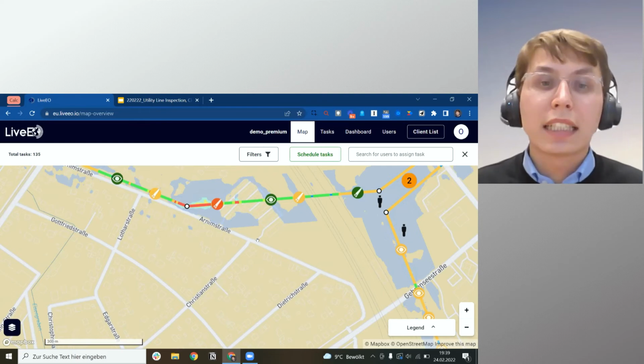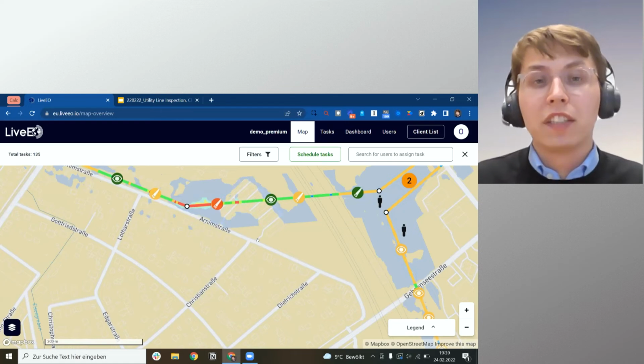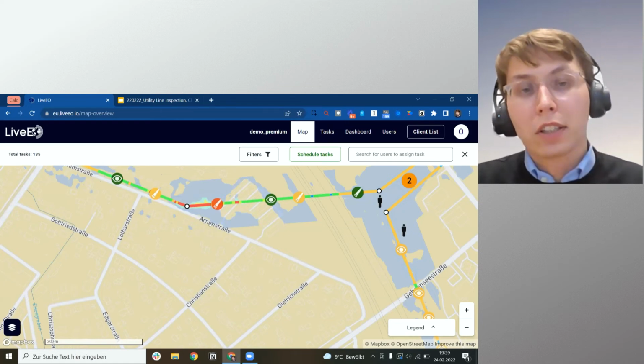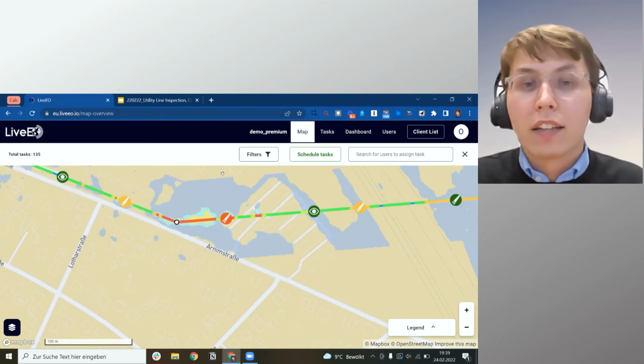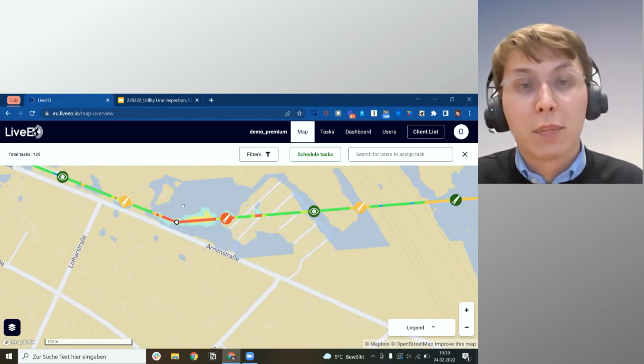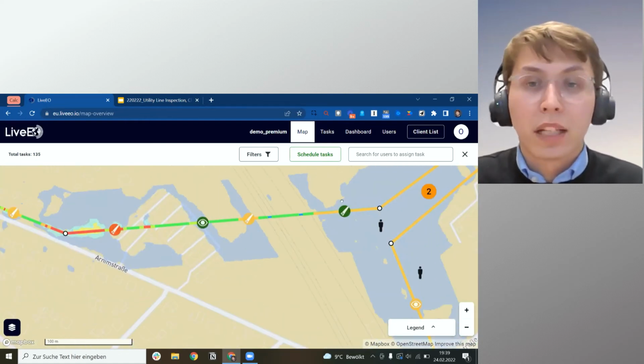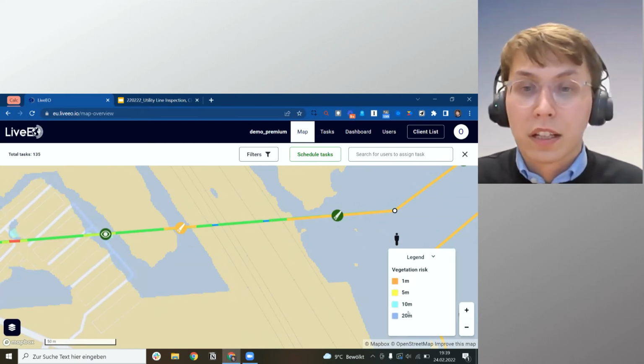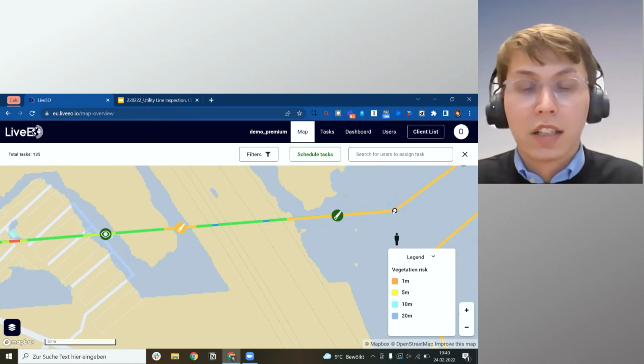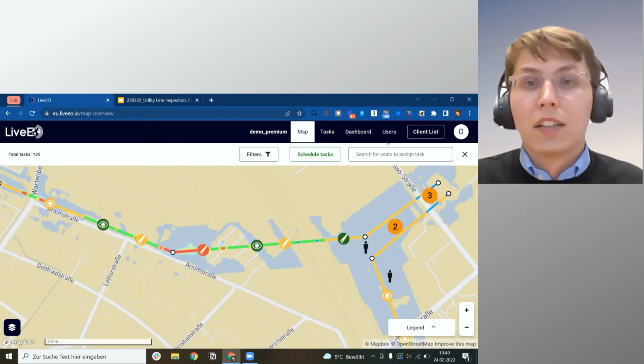And what we're doing is we're creating tasks, in this case, on a sub-span by sub-span basis. It could be on a span by span or feeder by feeder basis. We automatically prioritize these tasks based on the vegetation exposure of the asset. In this case, how high is the vegetation exposure of this part of the network? It's high because you have direct undergrowth from here, versus, for example, other areas where you have no risk because vegetation is low. That's why in this risk categorization, there's a distance of more than 20 meters from the overhead line, because it's also on the side, close to the pole. So there's no danger here. So what can you do with this?